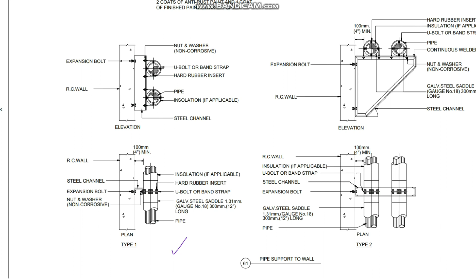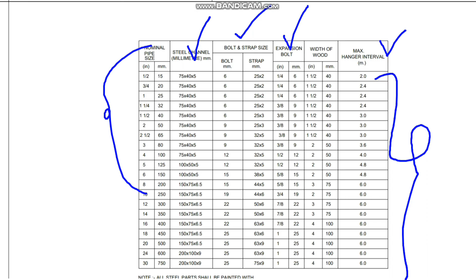So this U bolt, band strap, expansion bolt, and channel must follow the arrangement shown in this table. For different pipe sizes, they have given the steel channel size, the bolt and strap size, the expansion bolt size, and mainly the maximum hanger interval for each pipe size. You can see that as the pipe size gets higher, the supporting interval also gets higher.